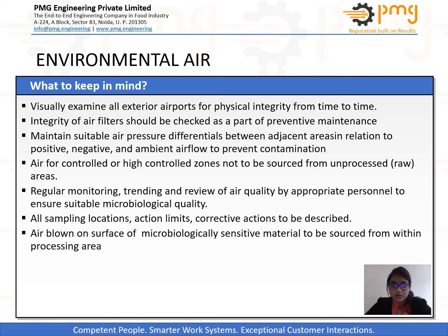Manufacturing or production areas need to be maintained at the utmost hygiene as the product comes in direct contact with the environment. In manufacturing areas, certain preventive actions are required to be implemented so that desired quality of the product can be achieved. These measures include: first, regular monitoring, trending and review of air quality by appropriate personnel for ensuring microbiological quality of the air. Second, maintenance of suitable air pressure differentials between adjacent areas — positive, negative and ambient airflow — to prevent contamination. High hygiene areas should always be maintained at positive pressure so that whenever any door or window is opened, air automatically flows from high hygiene areas to low hygiene areas.